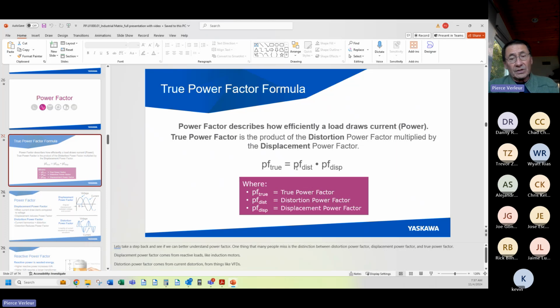How do we fix the grid short term? We improve the efficiency of the power delivery. Therefore, we have to deliver less power to do the same work, to cool the same building, to run the same industrial plant. That becomes on the end user. The end user has to fix that problem. The power company is going to motivate them to do so with money. They're going to say, if you don't fix your power factor, your power rate goes from 12 cents a kilowatt hour to 22 cents a kilowatt hour. So that differentiated rate structure is going to cause people to say, whoa, I don't want to give the power company that money, so I'm going to invest in new equipment. And that's the way the process should work, and in this case it is.